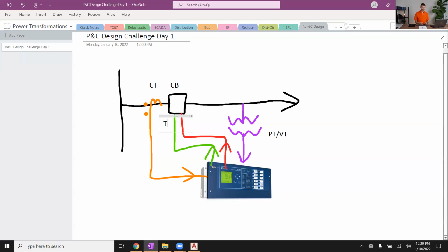So green is T for trip. And then the red over here is C for close. A lot of times at higher voltages, our breakers have more than one trip coil. We might have a trip coil 1 and 2 used for a primary and a backup relay. It gives us a level of redundancy in case one of those trip coils were to burn up or go bad and not function, so that we could hopefully count on the other trip coil to operate.